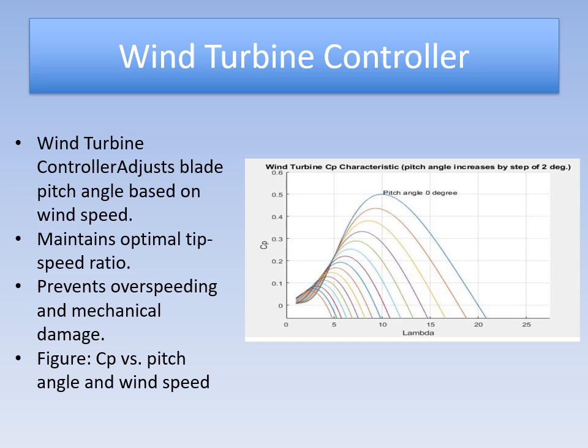Now let's zoom in on the wind turbine controller. This controller dynamically adjusts the blade pitch angle based on wind speed to maintain an optimal tip speed ratio. Doing so helps the turbine extract the maximum possible energy from the wind. It also prevents overspeeding, which could otherwise damage the turbine. The graph in the slide shows how the power coefficient CP varies with both pitch angle and wind speed, guiding the control system in making adjustments in real time.